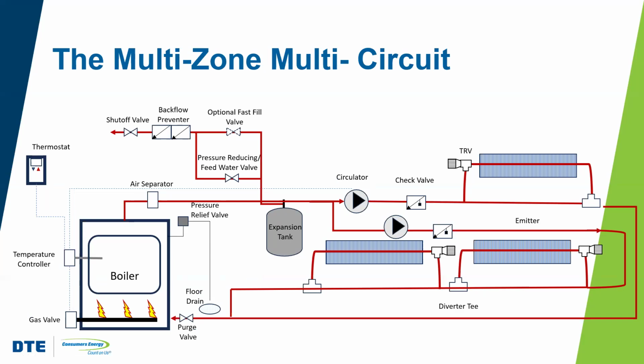The multi-zone, multi-circuit system. Here we can see that we've got branch piping, right? So here we have a separate circuit for each zone, and you can do this a couple of different ways. The drawing here shows it with separate pumps. It could also be with a single large pump and individual zone valves, right?